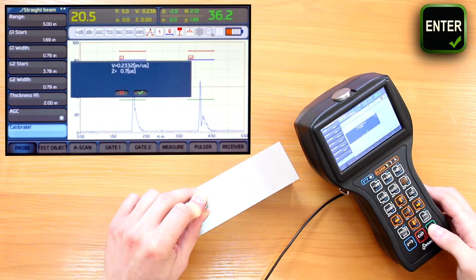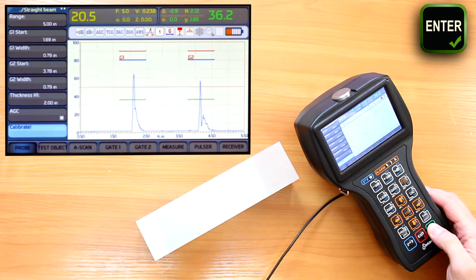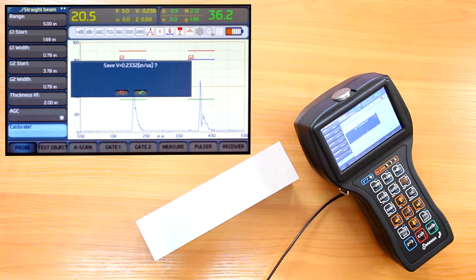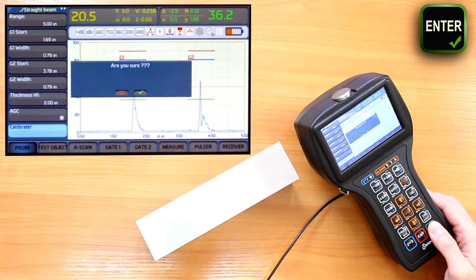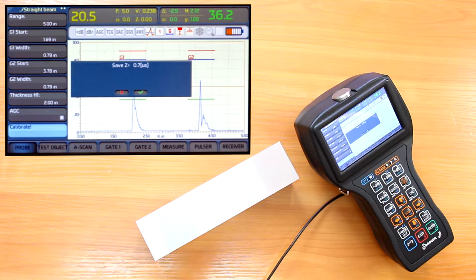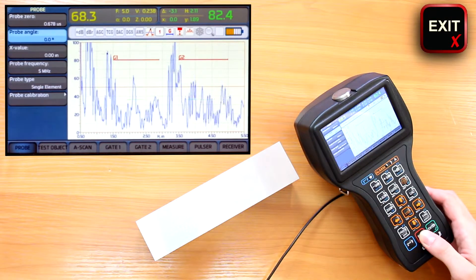The display will show the calculated values of probe zero and sound velocity. We confirm with the enter button. It then asks if we wish to save the calibrated value of sound velocity — if we used a test piece from the same material, it's a good idea to save this by pressing enter and confirming again. The same question is asked about the probe zero value, so we press enter twice to confirm it as well. The exit button gets us back from the calibration menu.